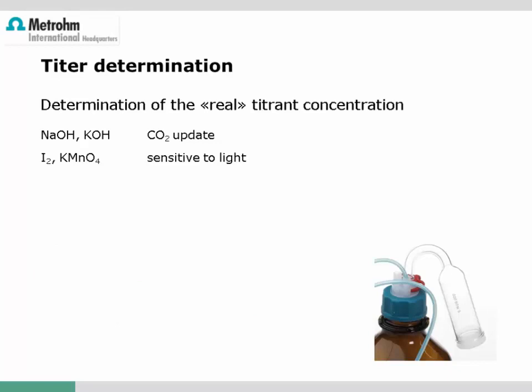What is the titer and how can it be determined? Usually a titrant solution is made by weighing a chemical substance into a volumetric flask and filling it up with solvent. The real concentration then has to be determined by titration using a primary standard. The main reason a titer determination is required is that concentration is not always stable. Alkaline titrants may absorb carbon dioxide, and others may face oxidation or reduction by light, causing the real concentration to decrease — this is called the aging of the titrant.